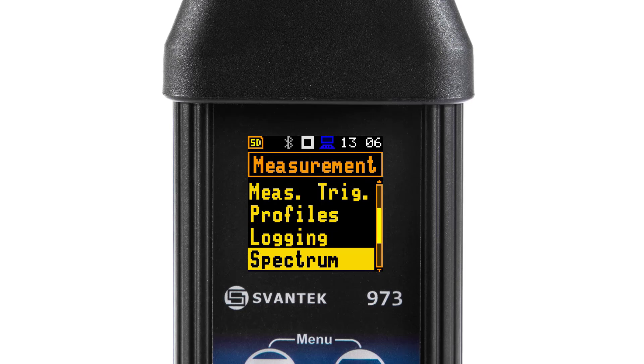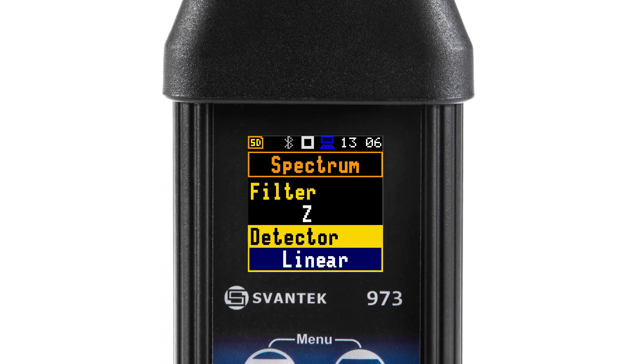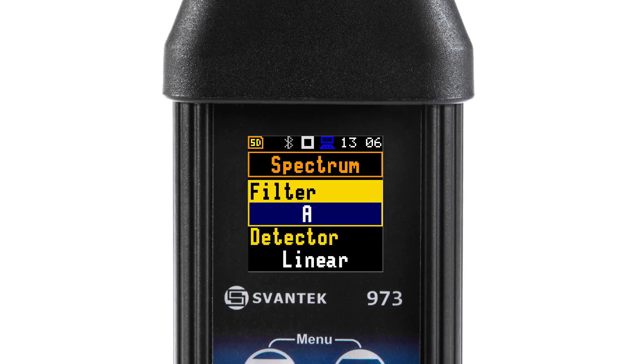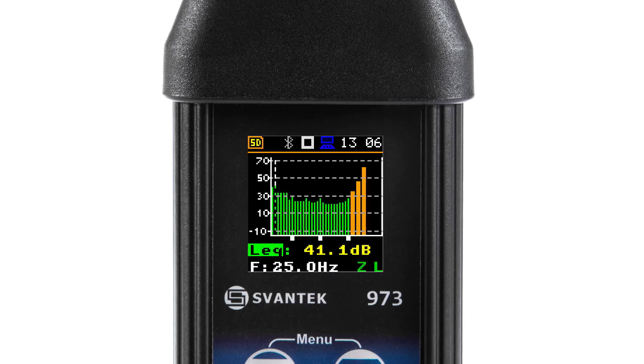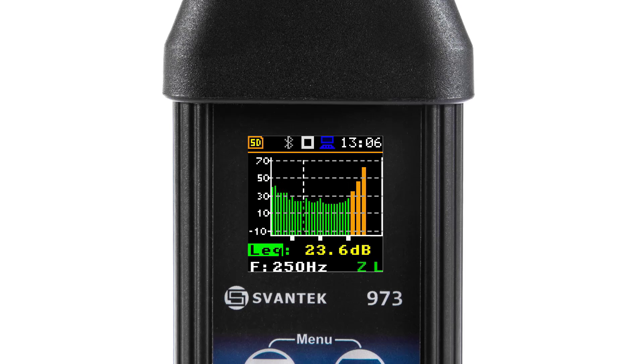The Spectrum position enables selecting the pre-weighted broadband frequency filter and the LEQ detector for the octave or third octave analysis. You can shift the Y axis up or down during the spectrum presentation with the up or down key. You can change the cursor position with the left or right key.